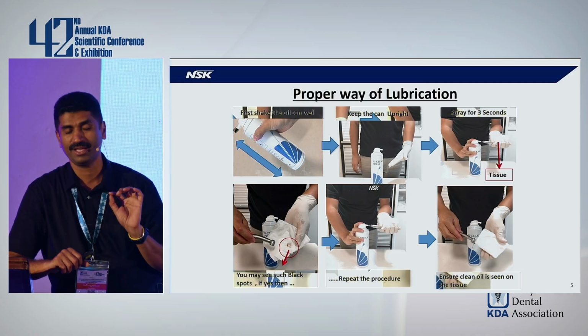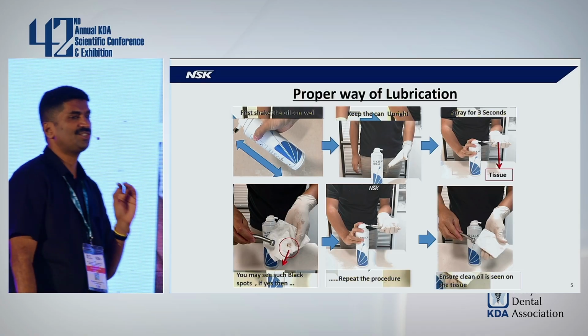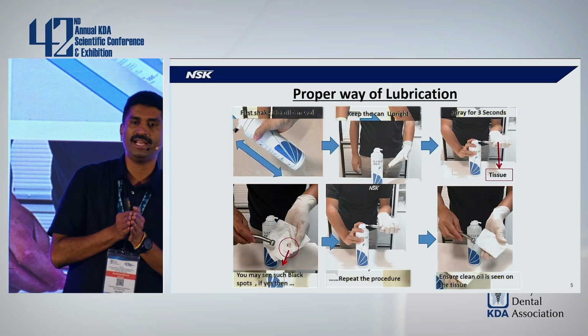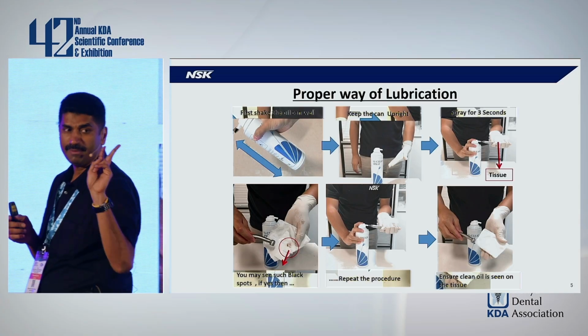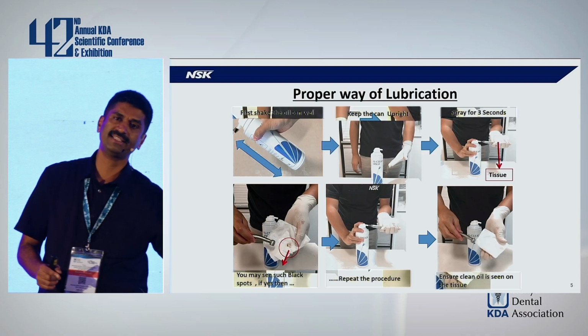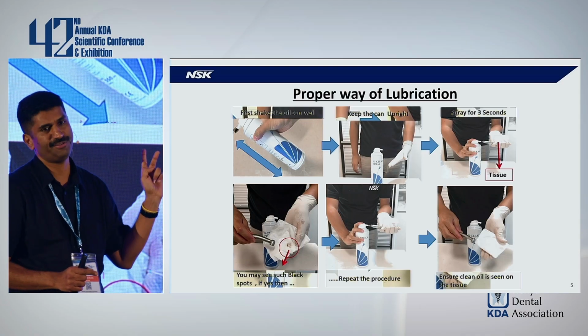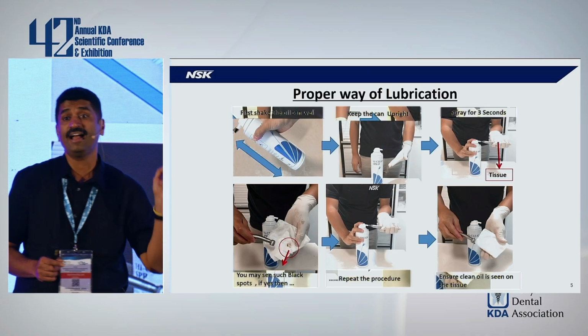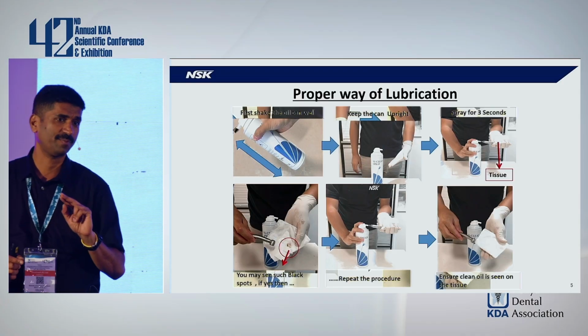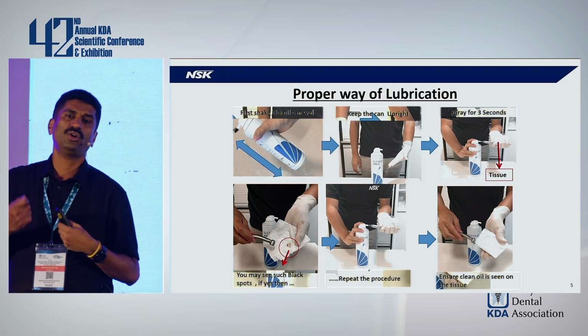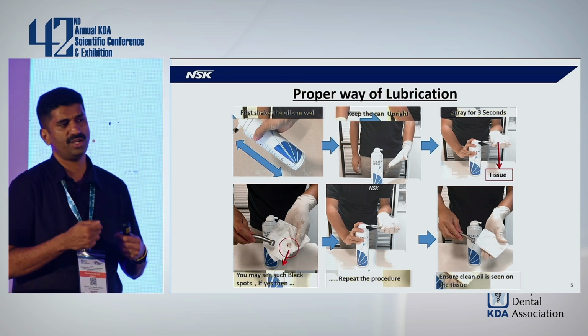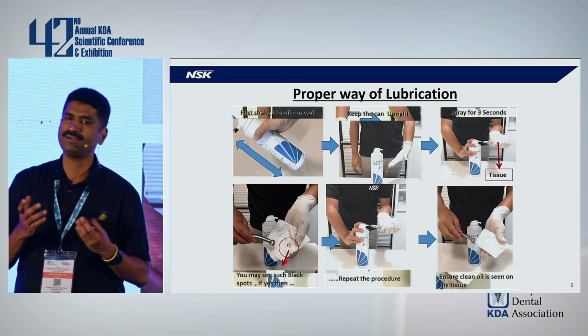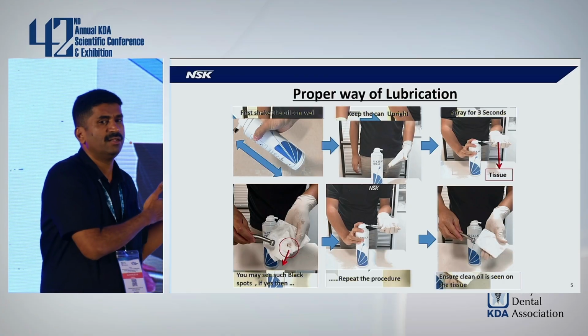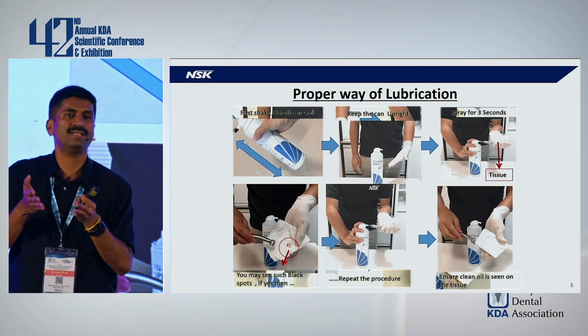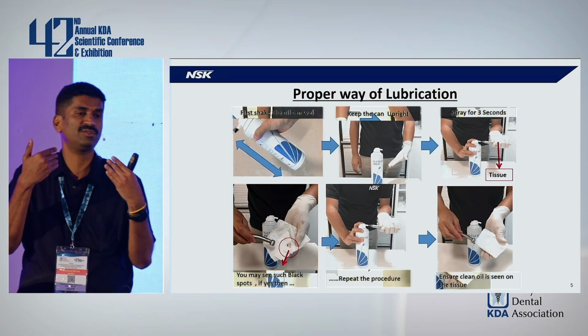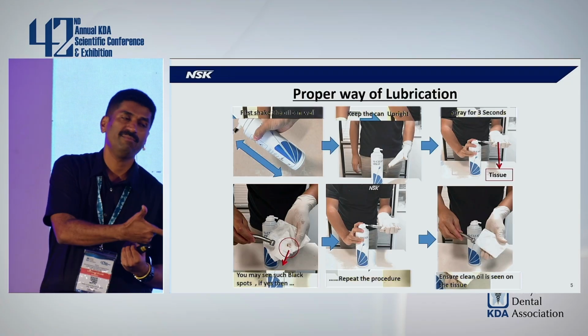Again, if possible. If not, then at least we recommend you to have a practice of lubricating 2 times a day, minimum. Once after the morning session and second after the evening session. Okay? And every time before autoclaving. It's up to you whether you want to autoclave your handpiece after every operation or once in a day or once a week, because autoclave has nothing to do with the maintenance or long life of the handpiece, whereas autoclave is only for the sterilization of the handpiece to ensure that your handpiece is sterile before working on the patient.